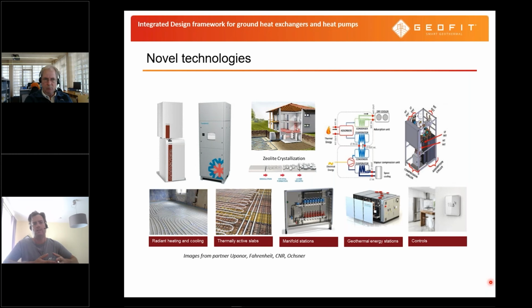It is called hybrid because it consists of a gas boiler, an adsorption unit, and a vapor compression unit. So the gas boiler here represents the heat source to drive the adsorption cycle. So not absorption, I mean adsorption, so not liquid, but a solid adsorption. This is then coupled to a compression cycle for space heating and cooling.